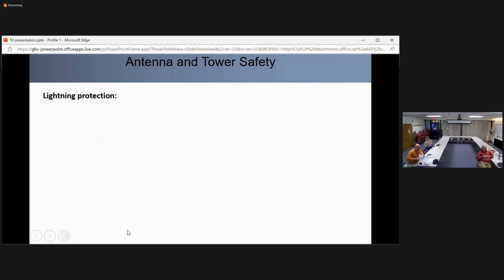What happens when you stick an antenna and or tower up in the air? It becomes a target for lightning. We're fortunate around here, we don't have as many lightning storms as you'll find in the Midwest, but you still have to be aware of the risks and what you can do to mitigate them, because there's a serious risk of both personal and property damage due to a lightning strike, and it doesn't have to be a direct strike.